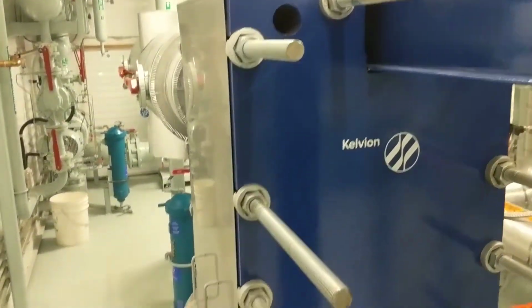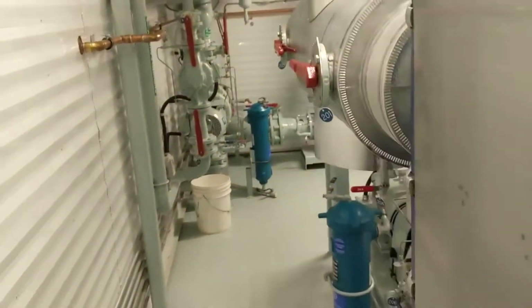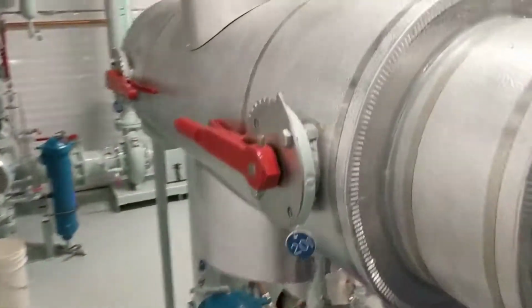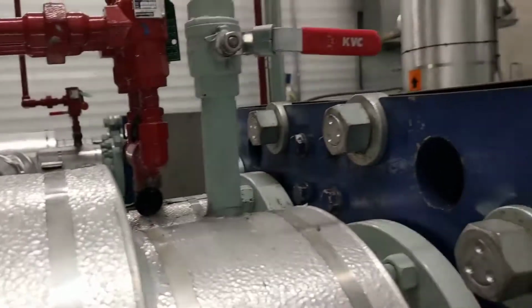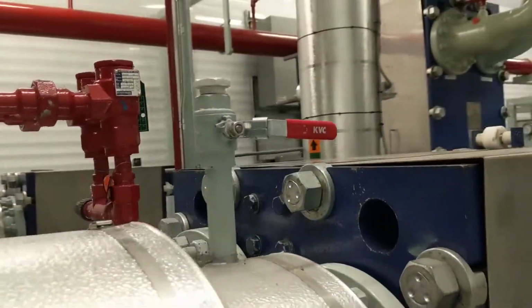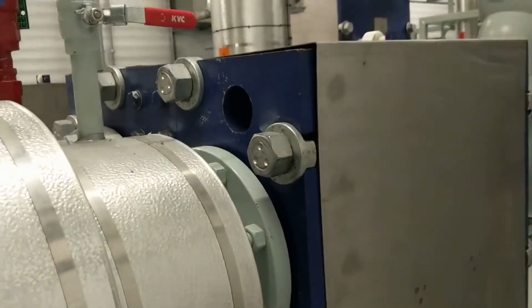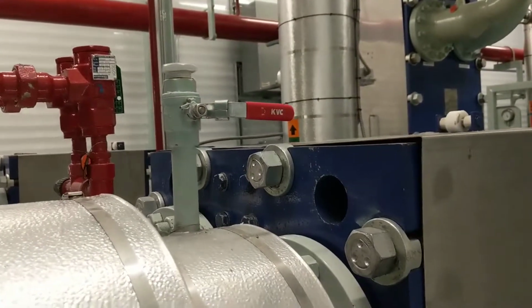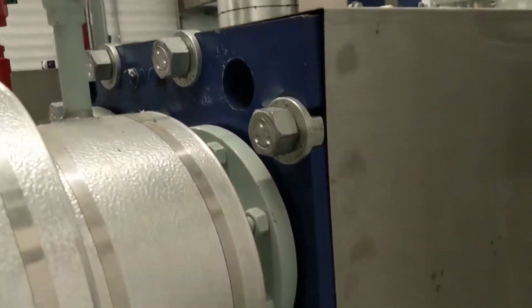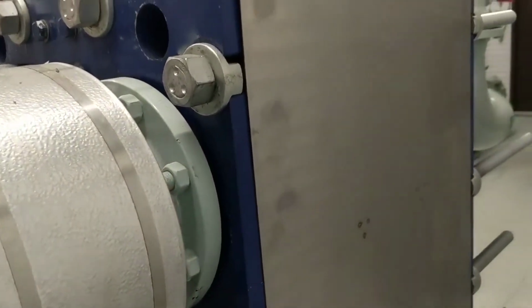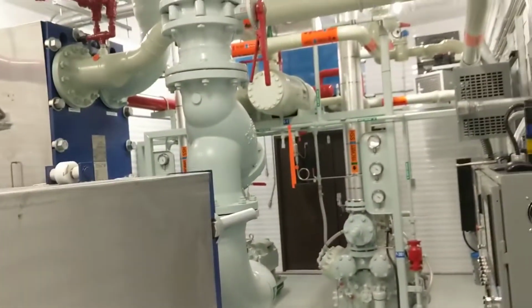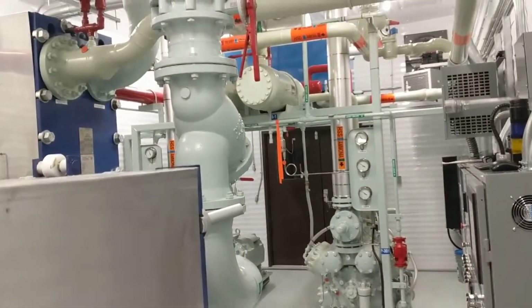On HX1 and 2, you've got ammonia and brine. And so you're using the ammonia to remove the heat from the brine as the ammonia is essentially boiled off using the suction from the compressors.